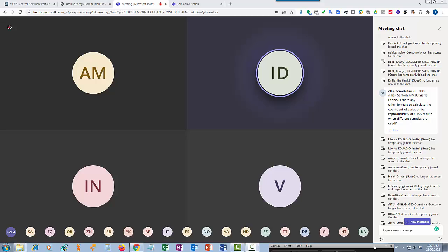panel of samples. So as we said, when you compile this repeatability panel of samples, so two highly positive, two in the low range, and one in the medium, you should test these samples with the new batch, just to verify that the performance of this new batch is comparable or equal to the one previously used.